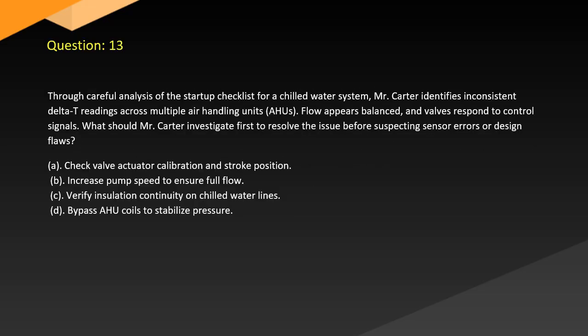Question 13. Through careful analysis of the startup checklist for a chilled water system, Mr. Carter identifies inconsistent delta-T readings across multiple air handling units, AHUs. Flow appears balanced, and valves respond to control signals. What should Mr. Carter investigate first to resolve the issue before suspecting sensor errors or design flaws? A. Check valve actuator calibration and stroke position. B. Increase pump speed to ensure full flow. C. Verify insulation continuity on chilled water lines. D. Bypass AHU coils to stabilize pressure.